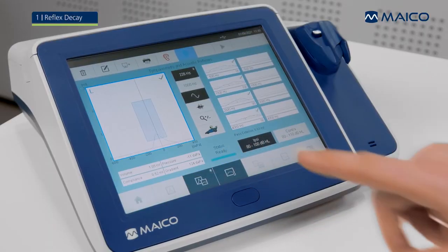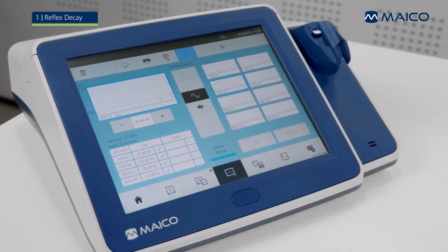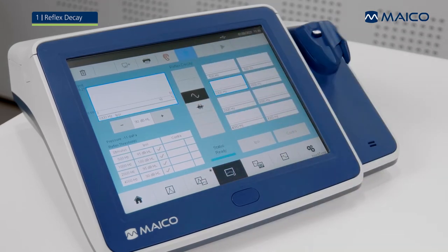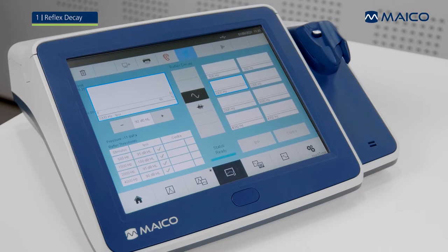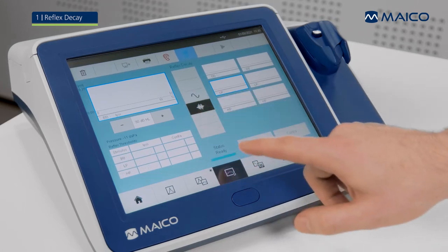Select the reflex decay icon on the home screen or in the function bar to go to the reflex decay screen. Choose the stimulus type by pressing on the stimulus type button. You can select between different tone and noise stimuli.